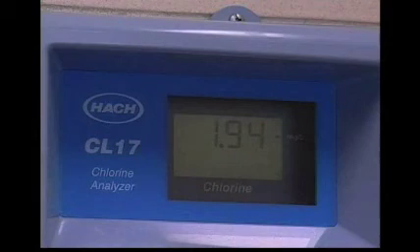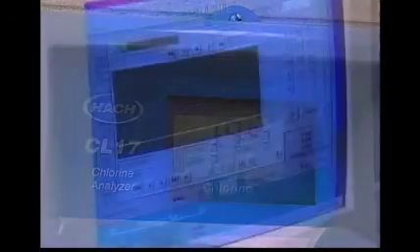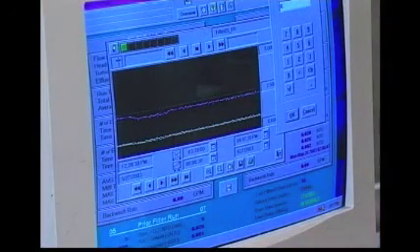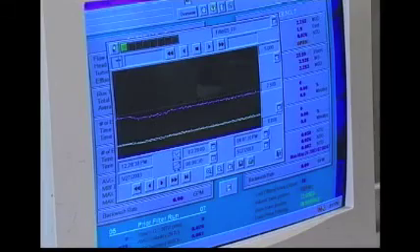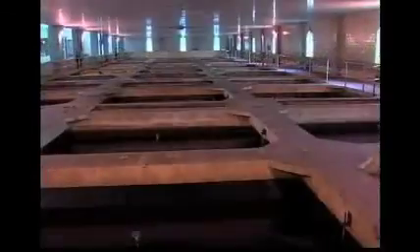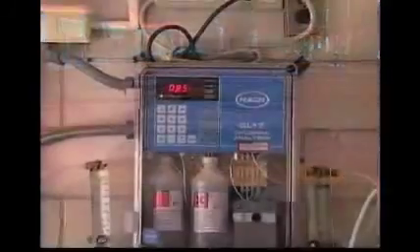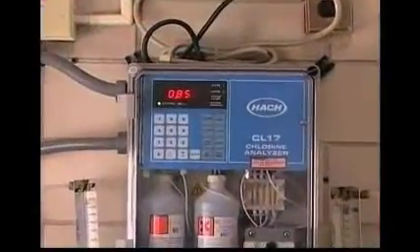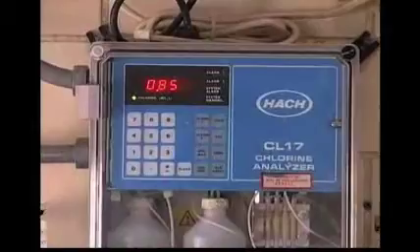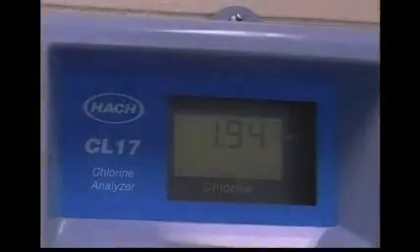Chlorine, a disinfectant, is added to the settled water at two different stages of the process to kill any disease-causing organisms that may be present. Water is initially disinfected after it leaves the raw water basin. A second dose of chlorine is added as it enters the filters. The water department doses at two stages to make sure that the water is always safe.